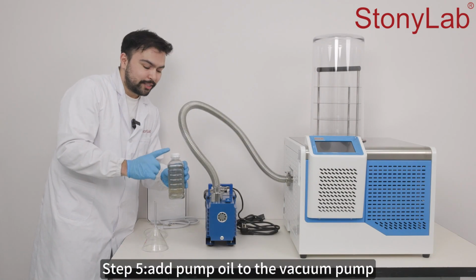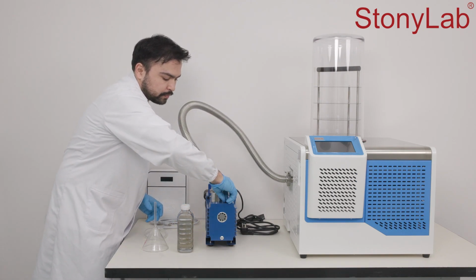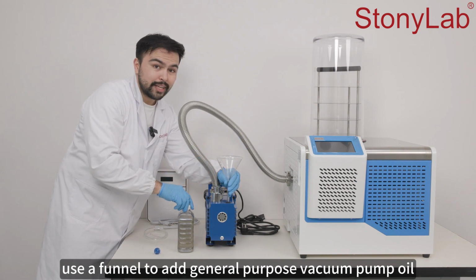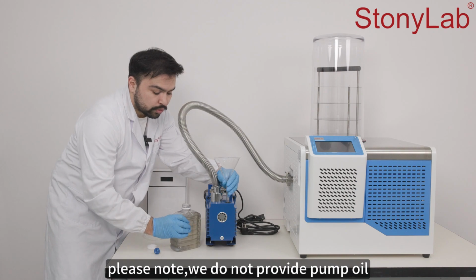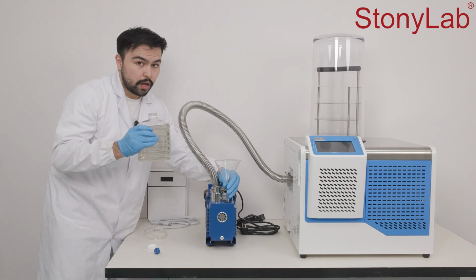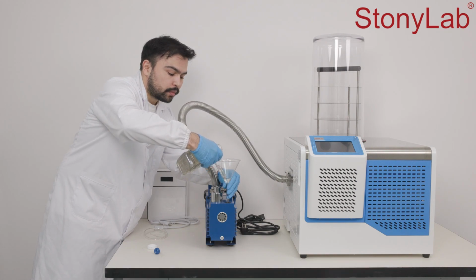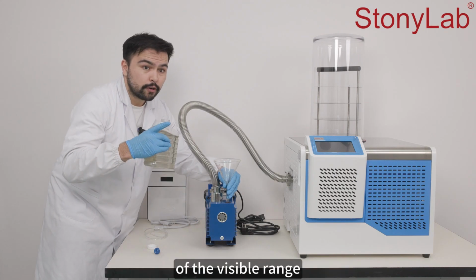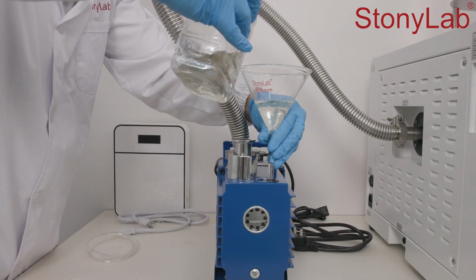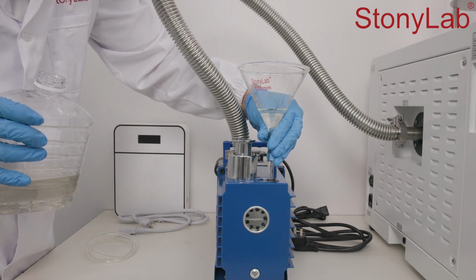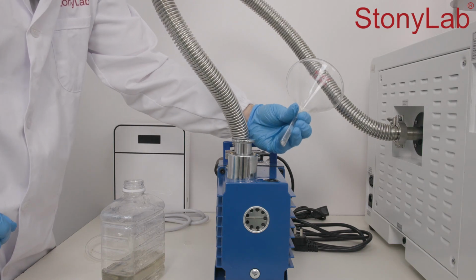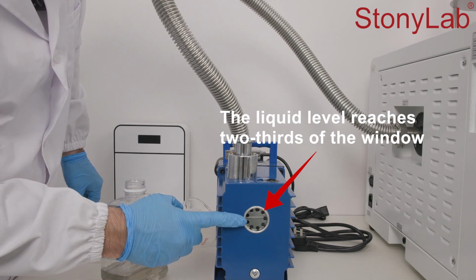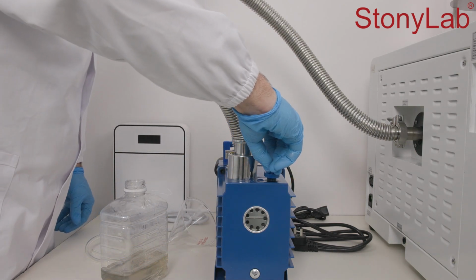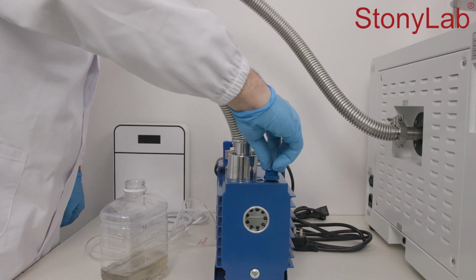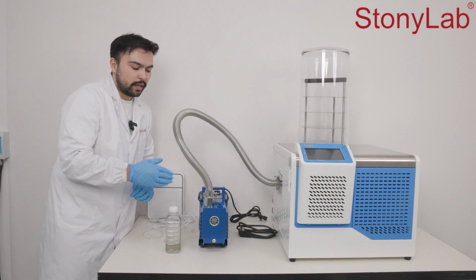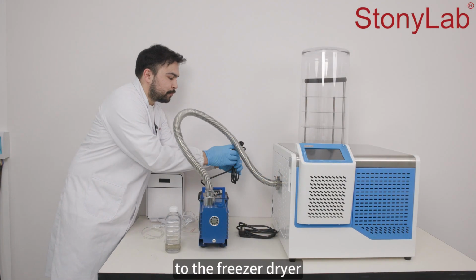Step 5. Add pump oil to the vacuum pump. First, open the oil fill port. Use a funnel to add general-purpose vacuum pump oil with a viscosity of 100. Please note, we do not provide pump oil. You need to purchase it separately. While adding oil, keep an eye on the oil sight glass. Stop filling when the oil level reaches above 2/3 of the visible range. Now once the fill port is closed, connect the vacuum pump's power cord to the freeze dryer.